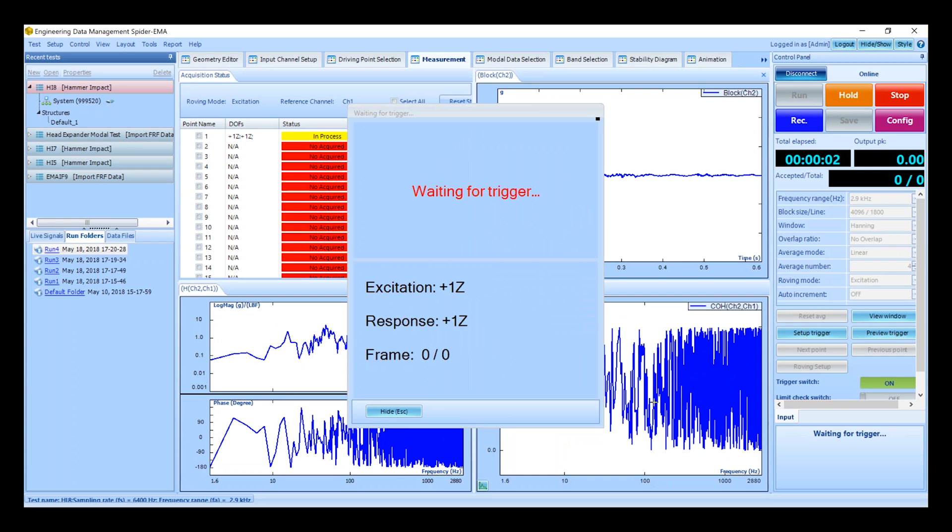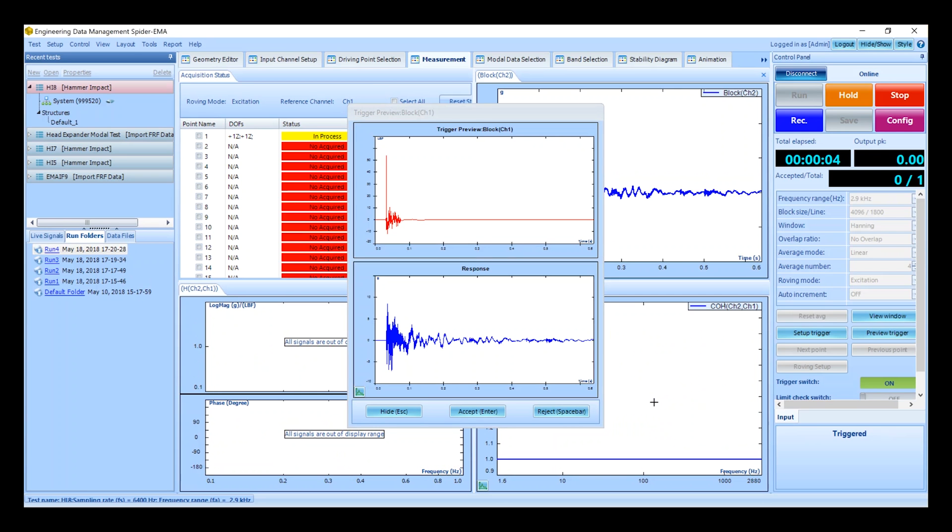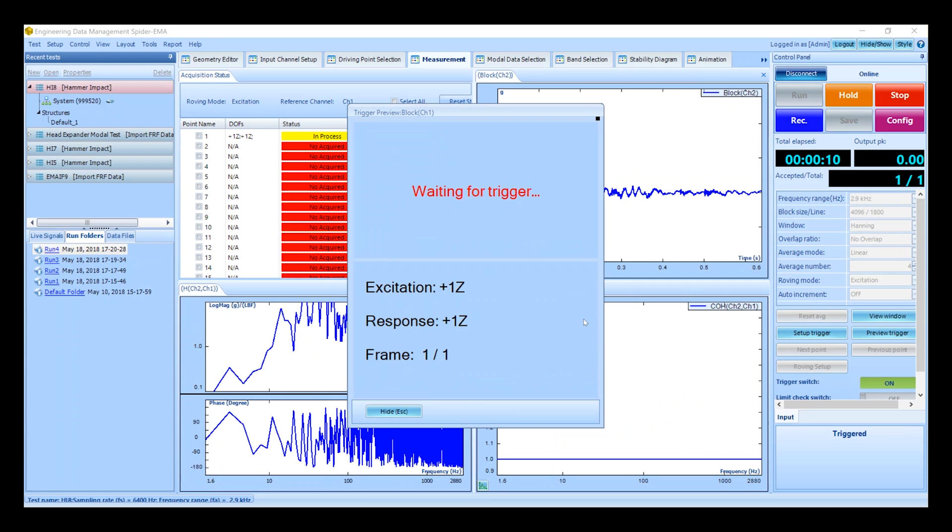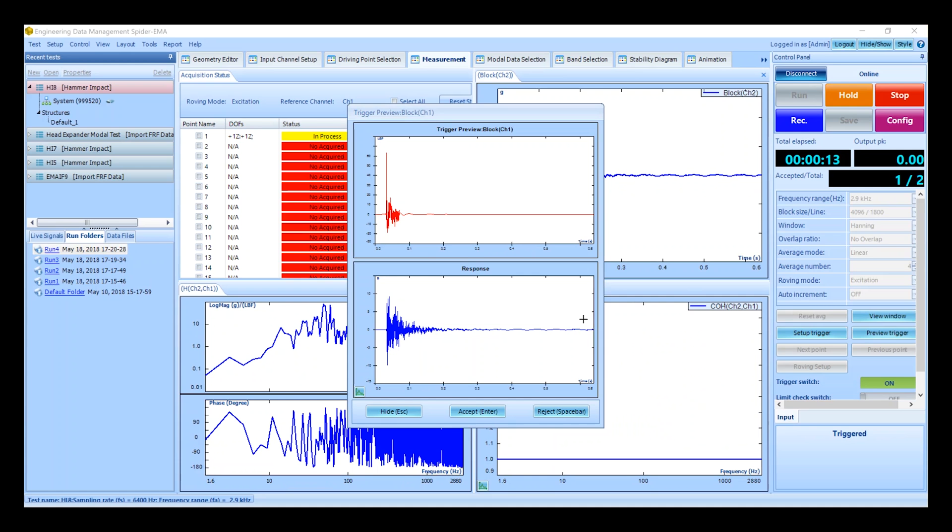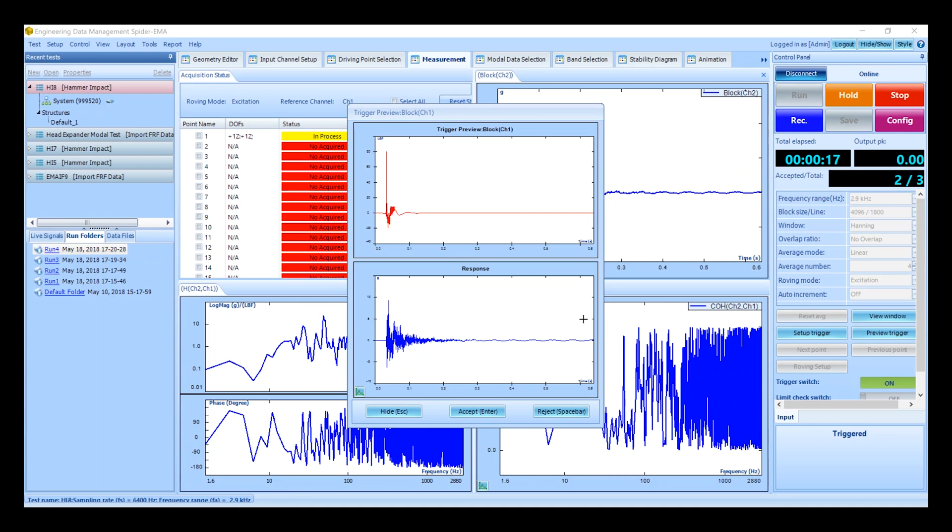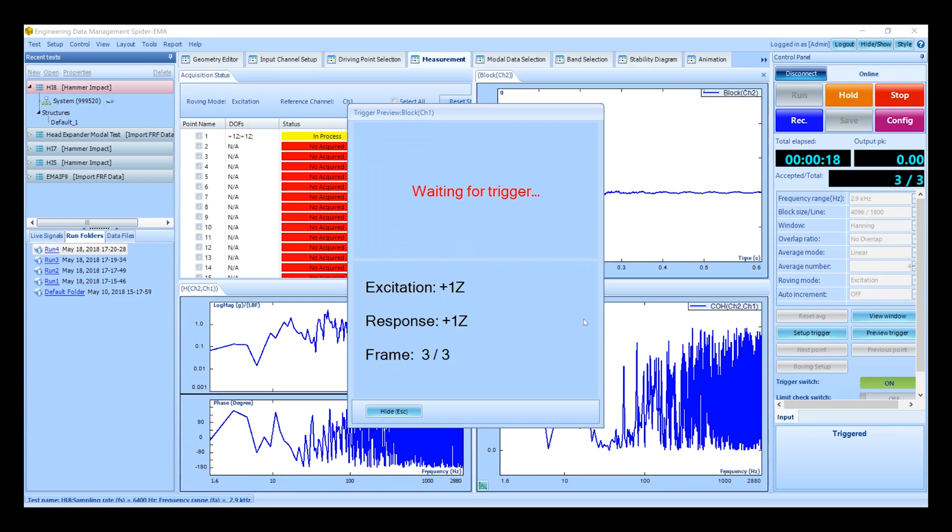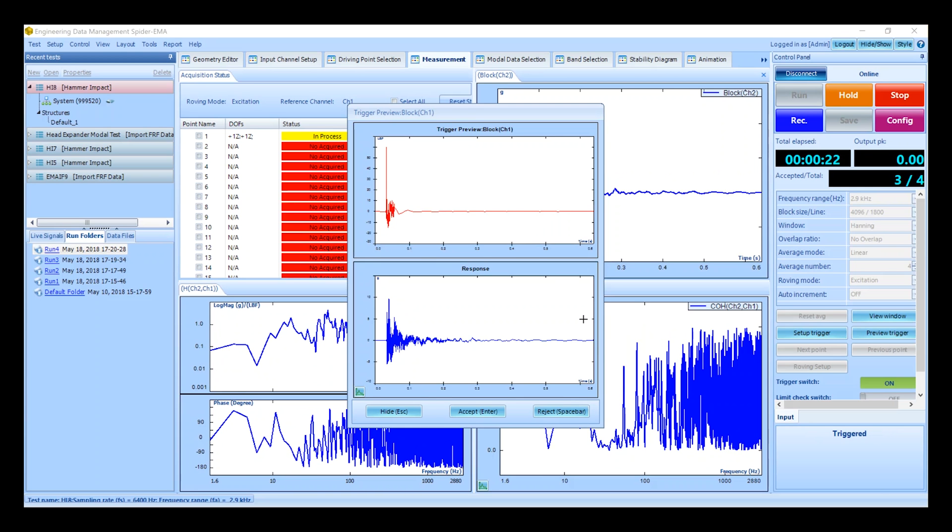The trigger window shows that it's ready to acquire the signal. Excite the structure using the modal hammer. The trigger preview window shows the measured impact and response signals. After reviewing the impact signal we can choose to accept or reject the signal. The rejected signals are discarded from the averaging process. Once we reach the average number the trigger window will close and the averaged FRF data will be saved.